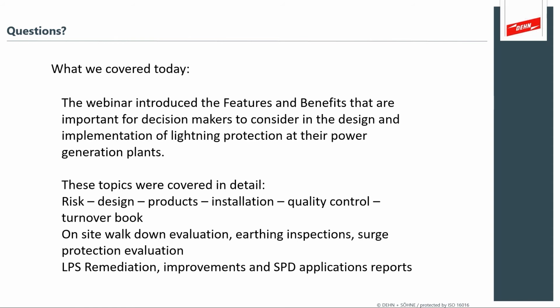So what the clamp-on meter shows you is that it's measuring a low impedance loop from the buried portion through a loop back to the exposed pigtail that we're measuring. It's a little bit confounding because what's happening is you're seeing the entire ground field. You're not actually measuring the impedance of the connection of that earth rod into the soil. Those are actually best conducted using the fall of potential methods with something like the brands Megger or Fluke offer, some very effective measuring equipment. Stephen, I'm not sure if you have some other points that you'd like to add to talk about the measurement of an individual rod relative to the soil, and that's where the 10 ohm connection comes from.